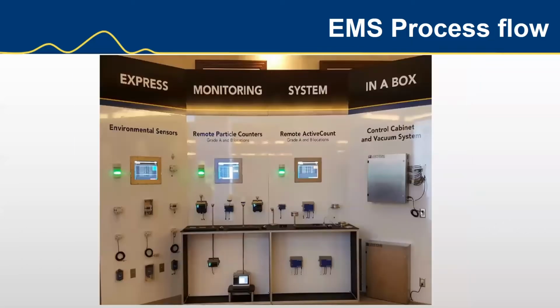Here we see one of our training facilities, and we have a full system running up here on clean room walls and the control cabinet. As you see over here, we have different sensors mounted differently, different types of mounts, portables connected to the system, environmentals, different types of connections, touch screens with the software running. We have alarm lights. So again, you can see we have environmental sensor wall, remote particle counter wall, air sampling. All this is for air sampling. We call it a remote active count.